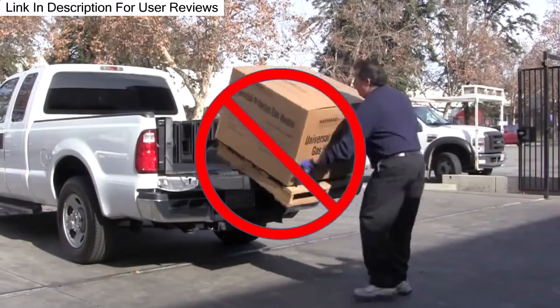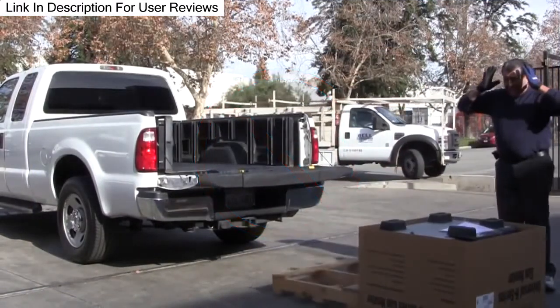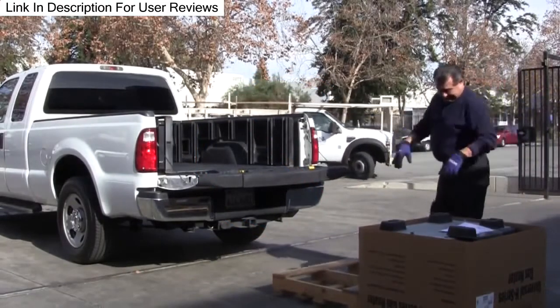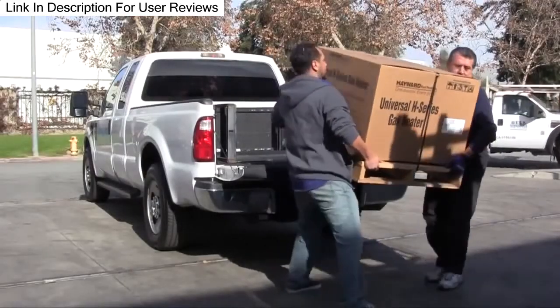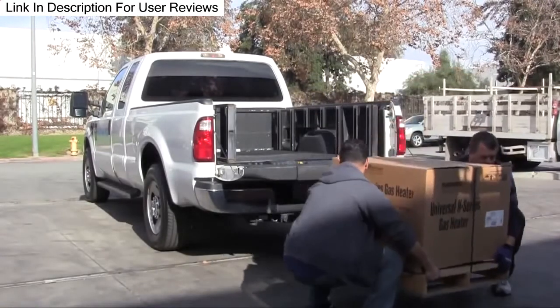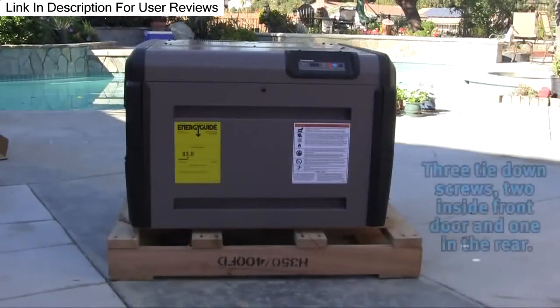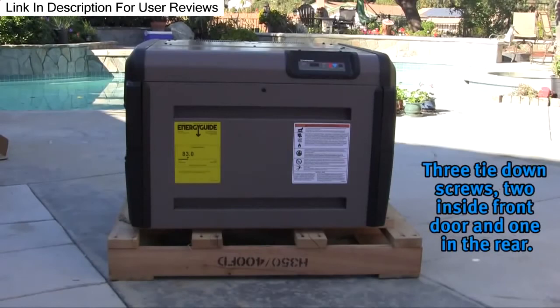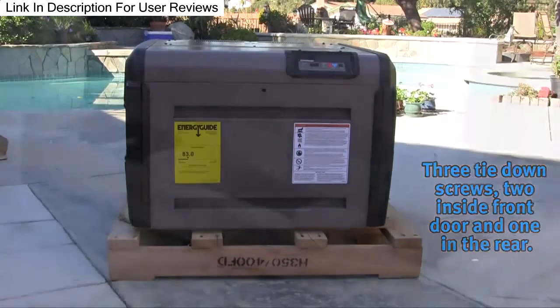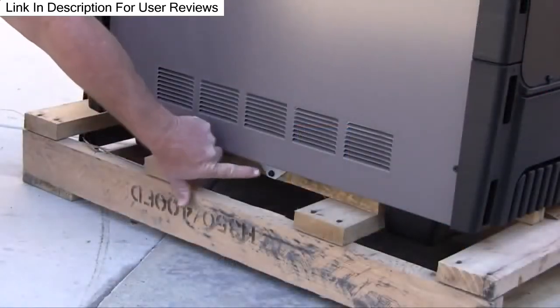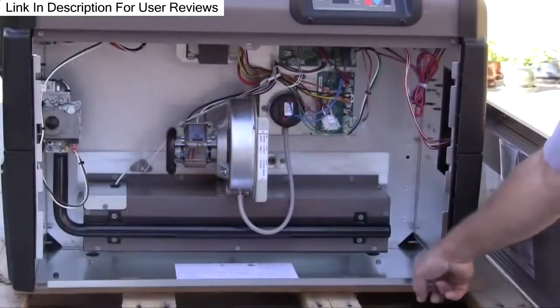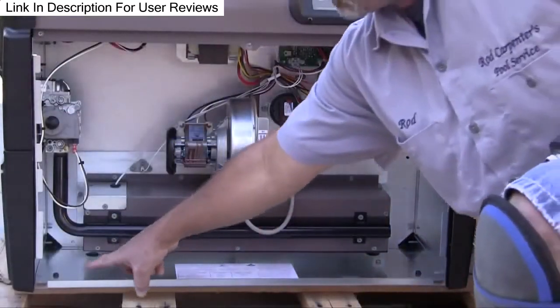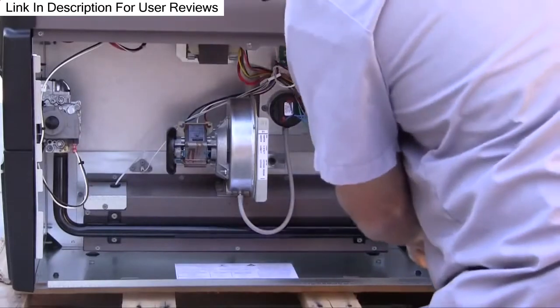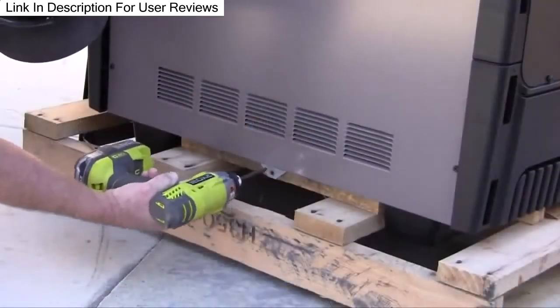Do not drop the heater from a truck tailgate to the ground. This may cause damage to the heater. Make sure you have the needed equipment or enough people to unload the heater properly. When uncrating the heater, you will find that it is tied down to the pallet by 3 screws, one located at the rear of the heater and 2 more located inside the front panel, which will need to be removed for access. Remove these screws and lift the heater off the pallet.